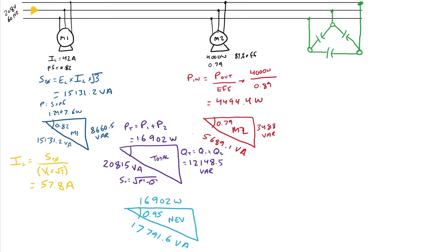Awesome. Now quickly while I'm here, I'm going to turn that into a current. So now my I line after correction. Same thing as before. I'm going to take 17,791.6 divided by 208 volts times root 3. And I will get my new current. So sorry, I don't have that one done. 17,791.6 divided by 208 times square root of 3 gives me 49.4 amps. So I have effectively reduced my incoming line current from 57.8 to 49.4.